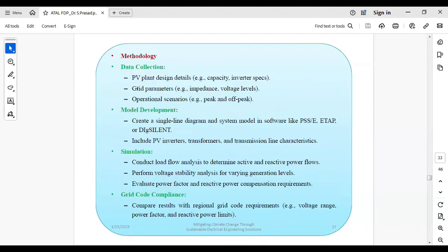So the other data: the PV plant SLD, you must have the grid parameters also, then the operating scenario. Okay, and different softwares we can use: PSSE, ETAP, DIgSILENT PowerFactory. More efficient softwares are specified by the CEA, according to CEA regulations we can use, and according to the grid code also. It will vary, depending upon the country's grid code. Okay, so different softwares they will mention, they will specify.